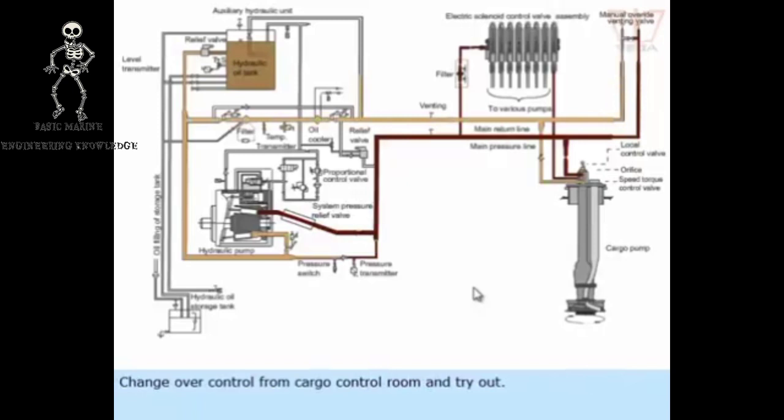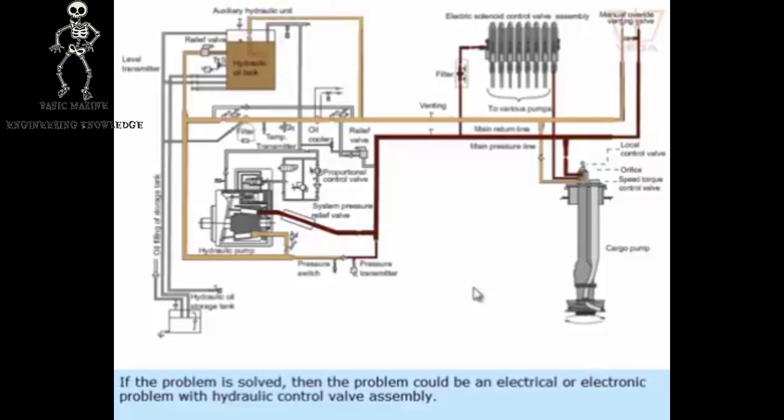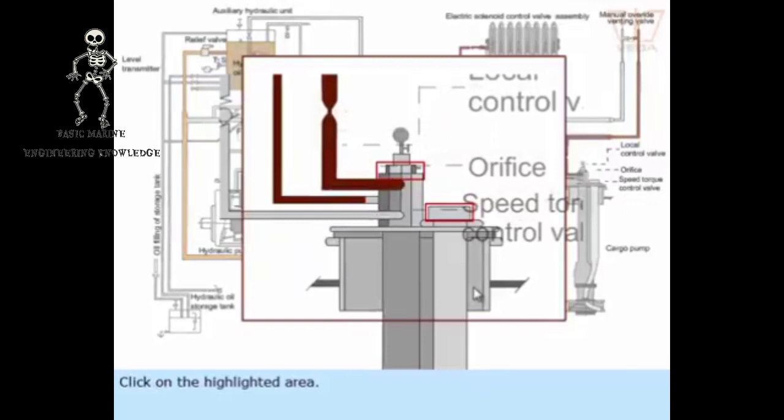Change over control from cargo control room and try out. If the problem is solved, then the problem could be an electrical or electronic problem with hydraulic control valve assembly. If the problem persists, what next? Click on the highlighted area.